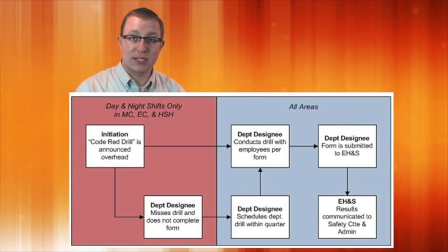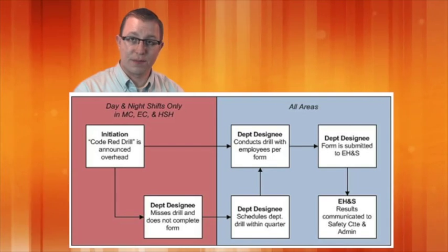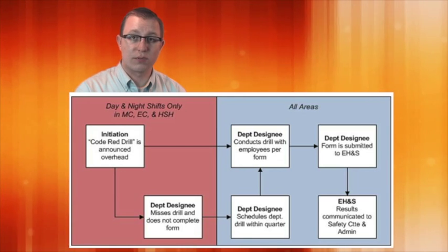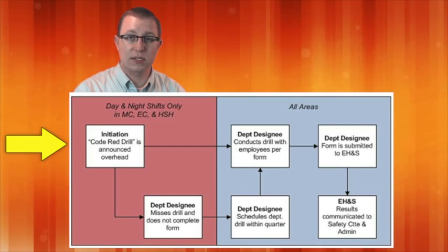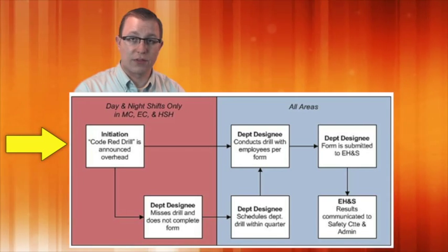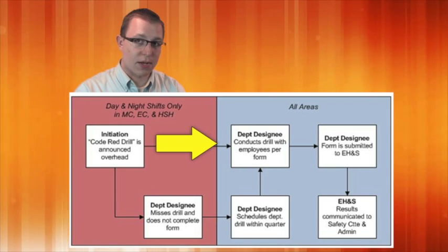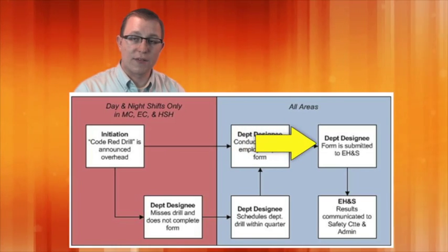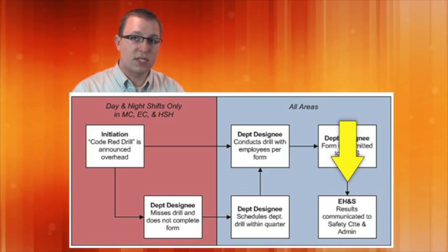Here's kind of the process of how fire drills are initiated. And it's a little different from business occupancies to healthcare occupancies. Healthcare occupancies wait for the alarm to sound. When that alarm sounds on a once per shift per quarter basis, then you go ahead and fill out the fire drill form, conduct a little scenario with your group. We'll talk about scenarios in just a second here. And then you get employees to sign in, send off that drill to us, and we report it on up to leadership.